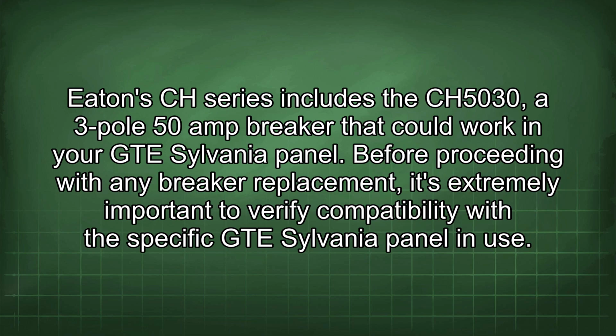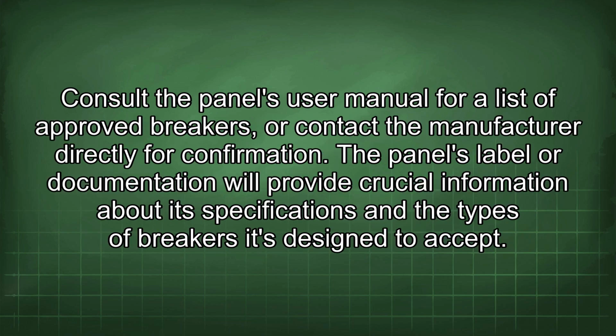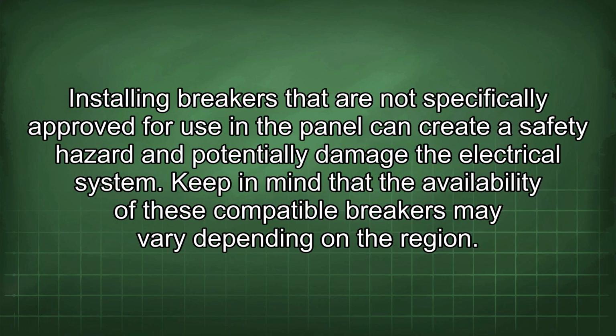Before proceeding with any breaker replacement, it's extremely important to verify compatibility with the specific GTE Sylvania panel in use. Consult the panel's user manual for a list of approved breakers, or contact the manufacturer directly for confirmation. The panel's label or documentation will provide crucial information about its specifications and the types of breakers it's designed to accept. Installing breakers that are not specifically approved for use in the panel can create a safety hazard and potentially damage the electrical system. Keep in mind that the availability of these compatible breakers may vary depending on the region.